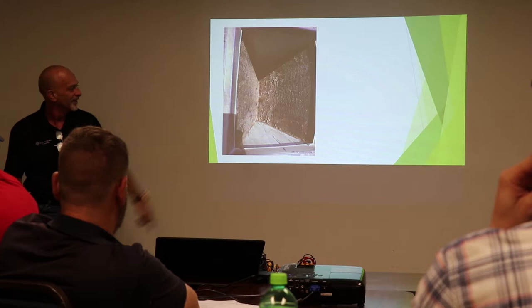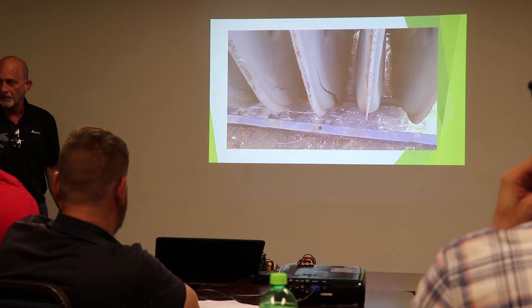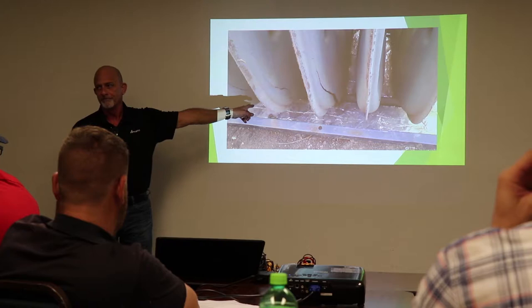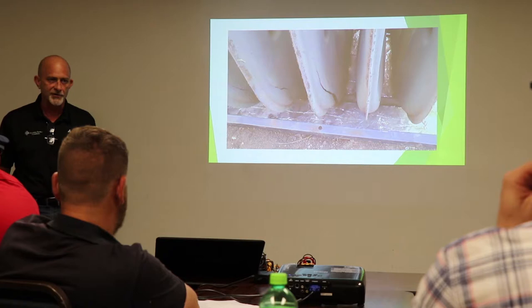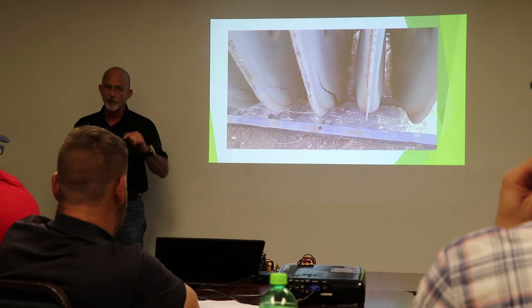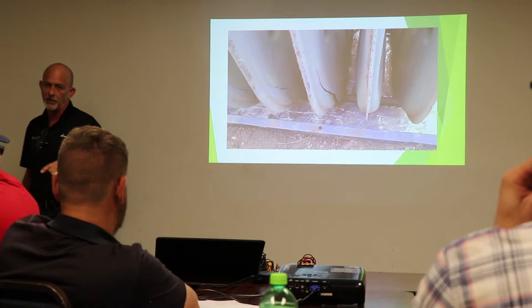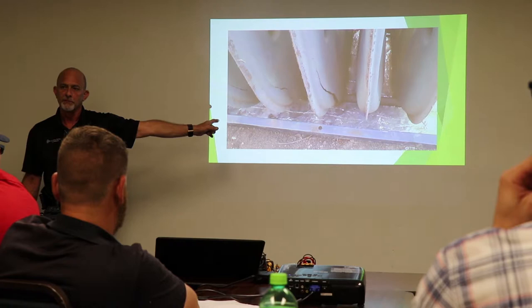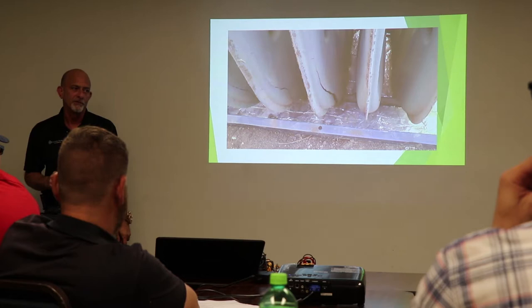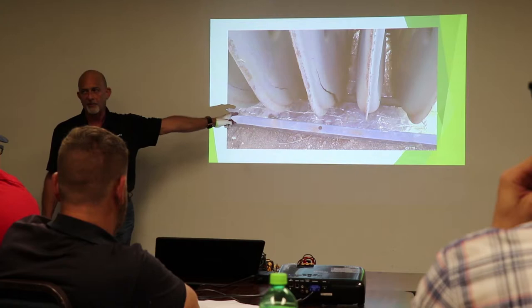All right, so we pull out our blower housing, we look up in there, right? That's an 80% heat exchanger. Guys, we don't need to go any further. If you're not selling furnaces, you better call your salesman right now to give this homeowner a price on a new furnace. Legally, guys, you're responsible to lock that furnace out. Disconnect the gas, disconnect the electric. If you leave this furnace operational, who's responsible? You are as a tech, not the company you work for, because you were the last person that touched it, and you left it operational. That will kill somebody. You're doing nothing but putting carbon monoxide in the house.